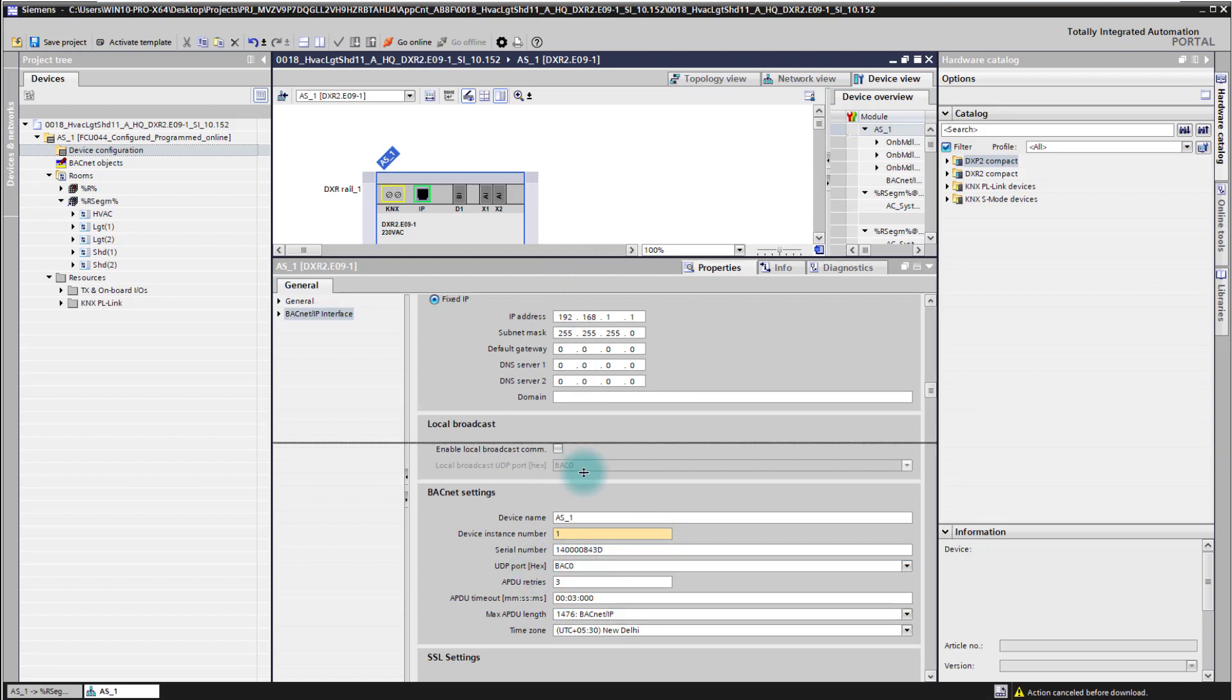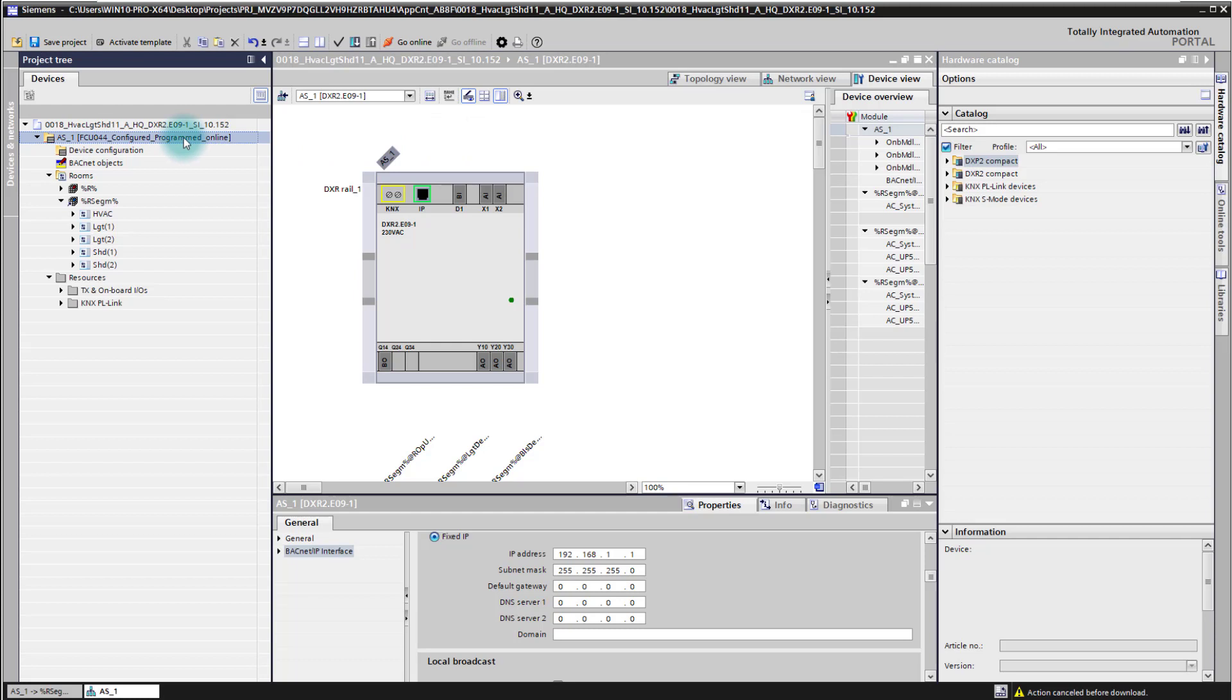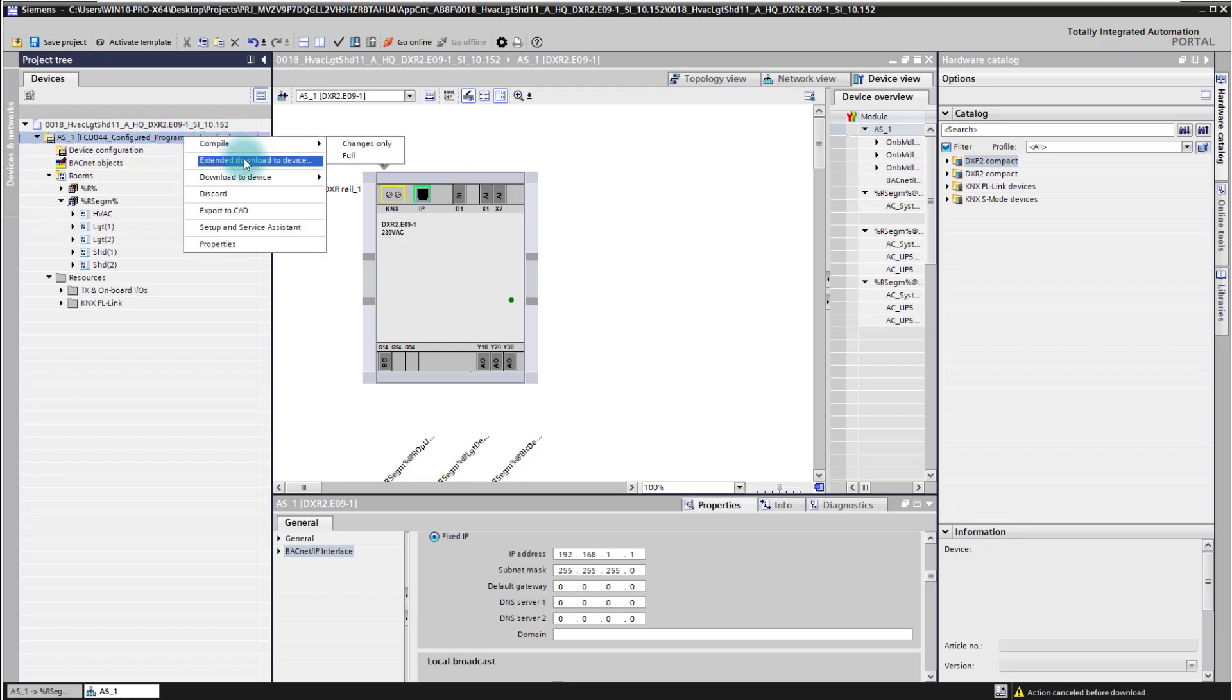As soon as this has been set and prepared we are able to connect to the device. First of all we need also to configure the device with the BACnet settings, and this is done on the controller here with a right click in the context menu, extended download to device.